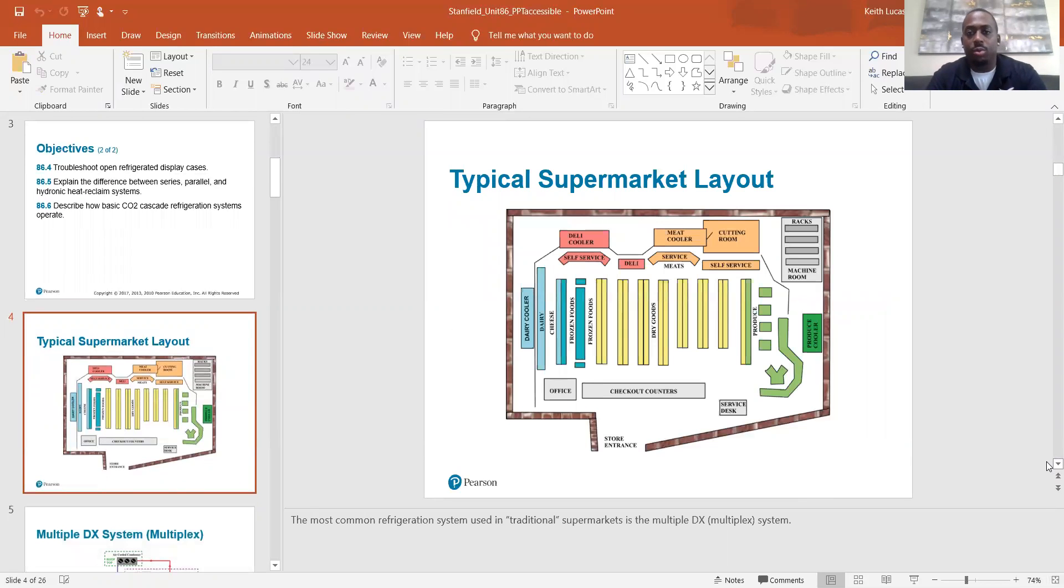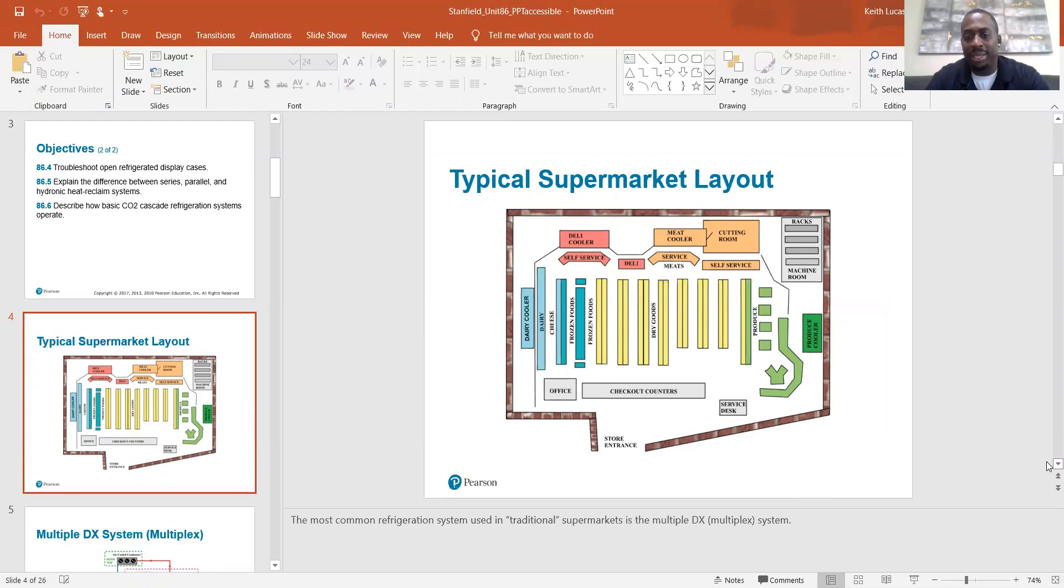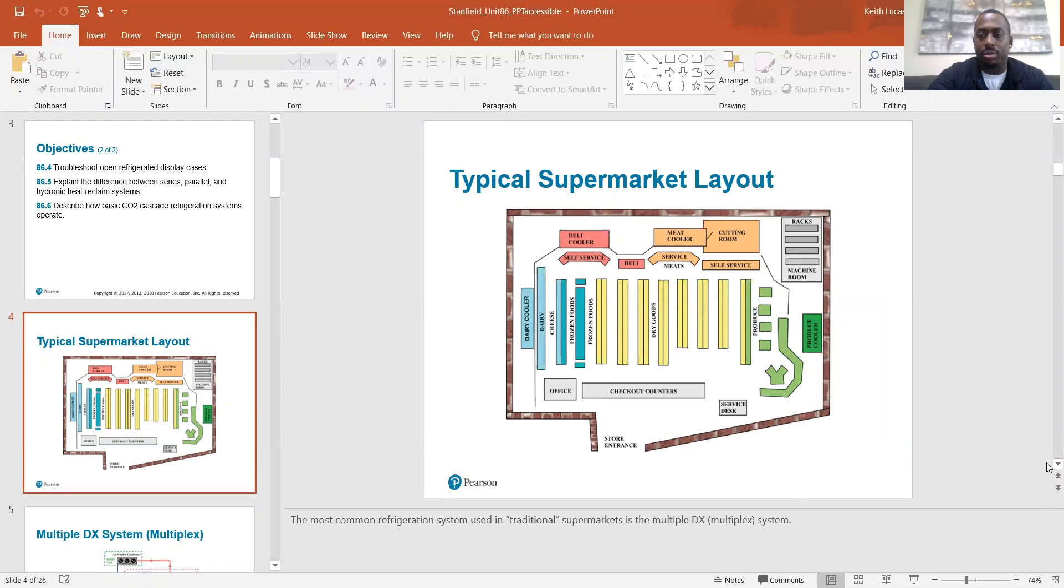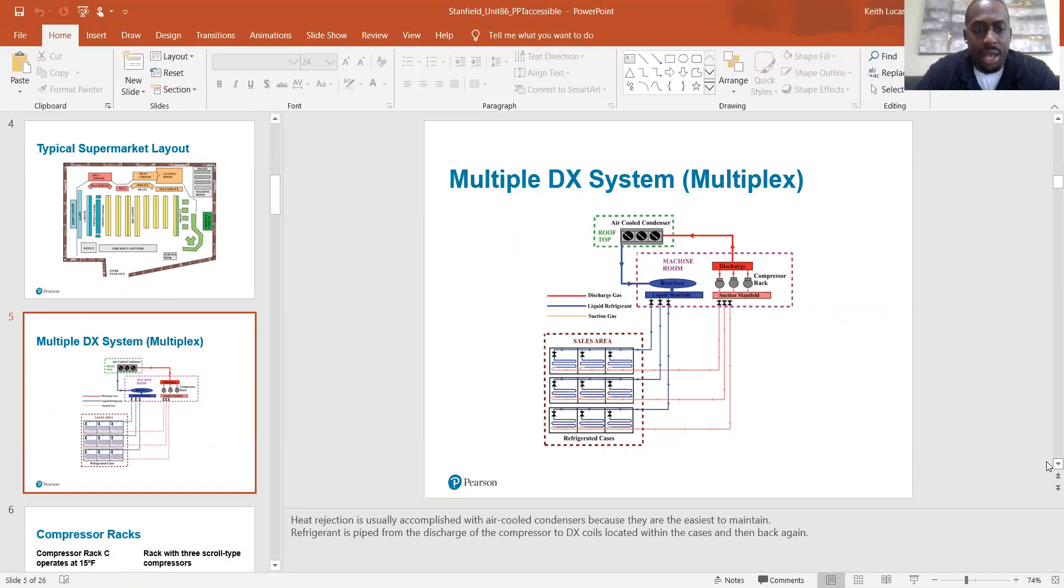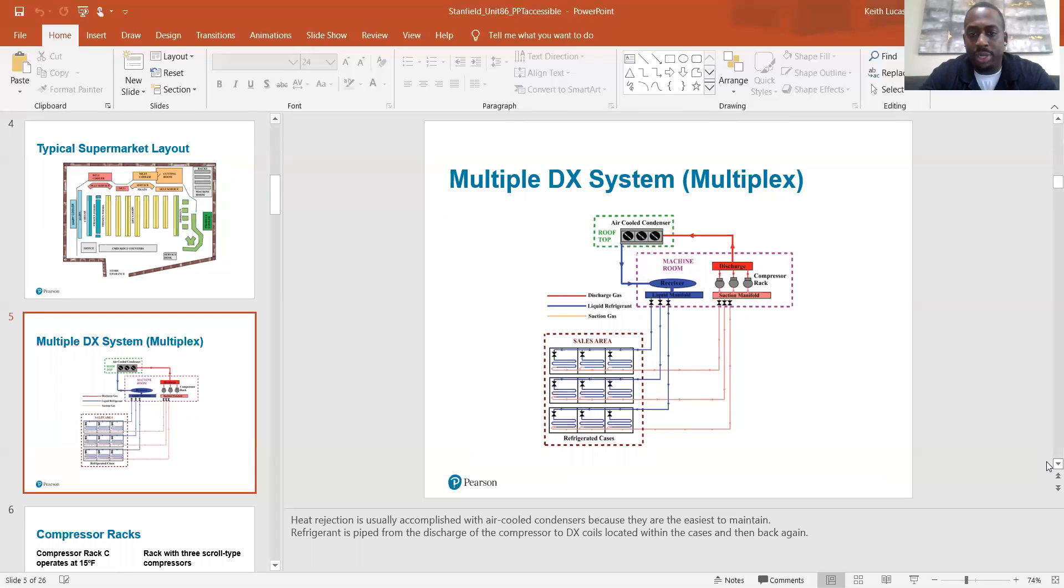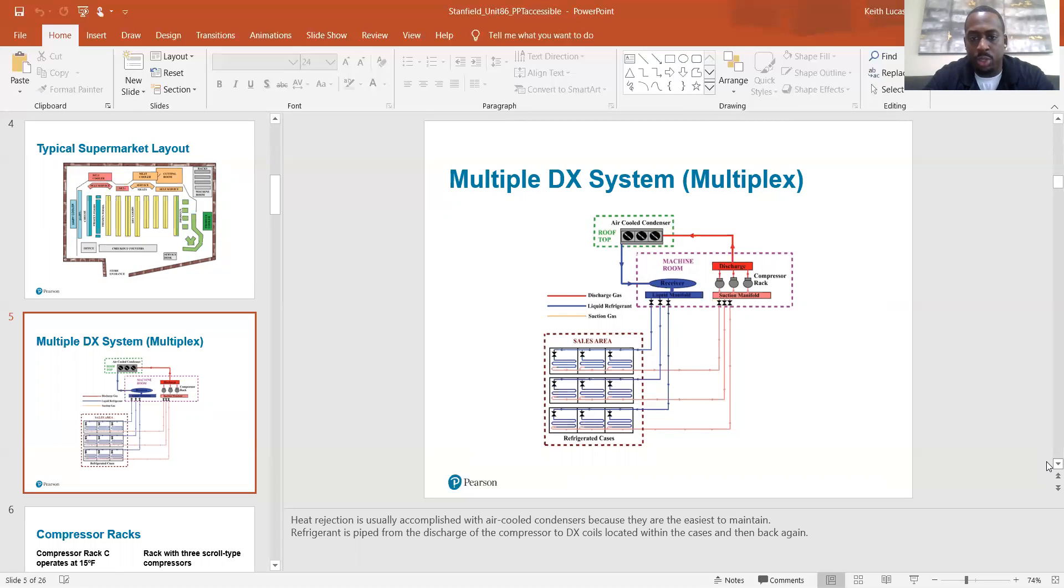So typical supermarket layout. Most common refrigeration system used in a traditional supermarket is the multiplex DX system or multiple DX system. Heat rejection is usually accomplished with air cool condensers because they are the easiest to maintain. Refrigerant is piped from the discharge of the compressor to DX coils located within the cases and then back again.